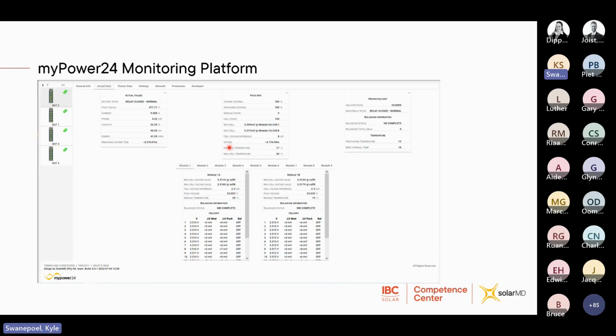So if you hover over each of these, it will tell you which cell or which battery module is the lowest and which one is the highest. In the protection state, the isolator is closed. So that is your mechanical isolator, and then your software disconnect relay is also closed. So we have a normal operation over here.